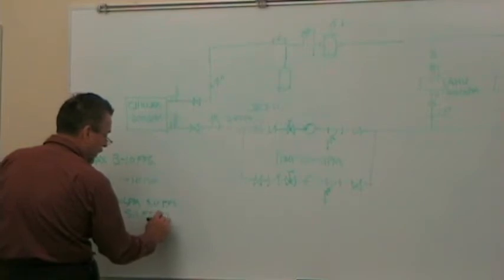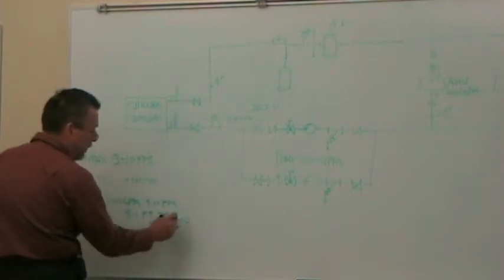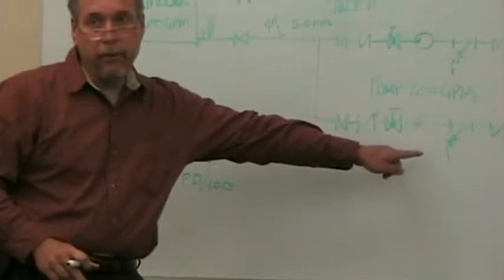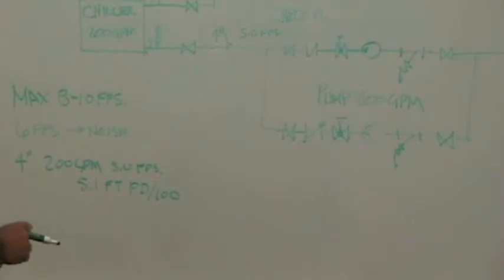And the pressure drop of a not necessarily clean pipe, but a pipe that's been in operation for some time, is so, 4-inch, 200 gallons per minute, 3.0 feet per second, and 5.1 feet pressure drop per 100 feet of pipe. So now I can start adding things up and start looking at how my pump is affected.